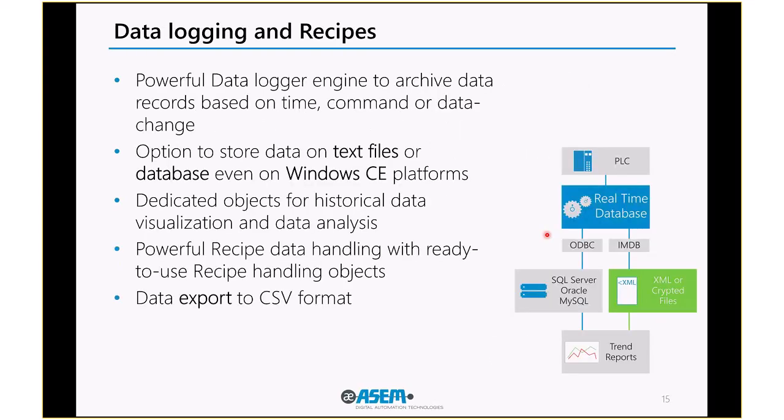Data logging. In Premium HMI, we have the possibility to record and store data. This we will see later, but it's important to know we have two possibilities in Premium HMI to store data. One is called IMDB, which is in-memory database, so basically a text file, very simple, very easy, very fast. The other one is ODBC, so the possibility to store data into relational databases.